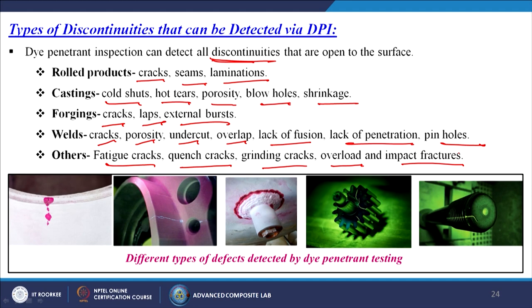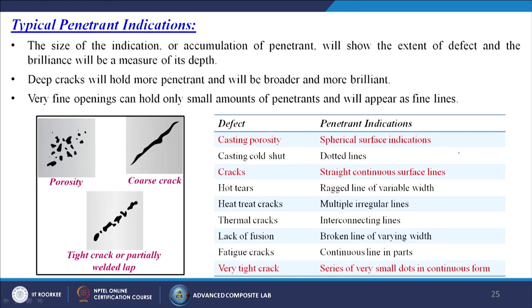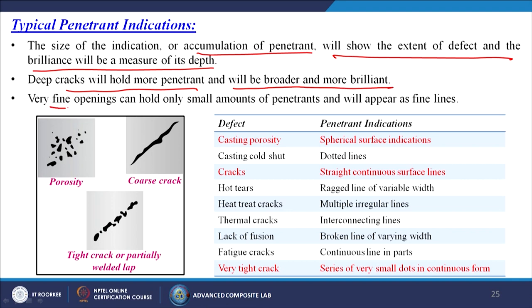Typical penetrant indications: the size of the accumulation of penetrant shows the extent of the defect, and the brilliance measures its depth. Deep cracks hold more penetrant and appear broader and more brilliant, while very fine openings appear as fine lines. Casting porosity shows as spherical surface indications; casting cold shut as dotted lines; cracks as straight continuous lines; hot tears as ragged lines of variable width or multiple irregular lines; very tight cracks as a series of very small dots.